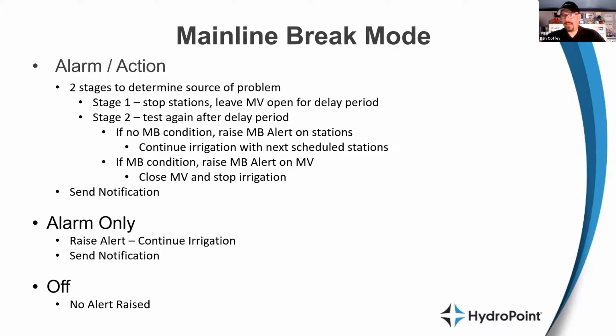First, when the alert is raised, the first thing the controller does is shut down any stations that are running without closing the master valve. So we turn off all of the irrigation that's running, but don't immediately slam that master valve shut. The benefit here is many, many times it is your irrigation system that pushed you past the limit. Maybe it was a stuck valve. Maybe it was a lot of breaks that just drove up your irrigation consumption on a station, that drove it past not only the station high flow alert, but way up past the mainline break. So the first thing we do is shut everything down that we can control and see if the measured value goes back down to 0.